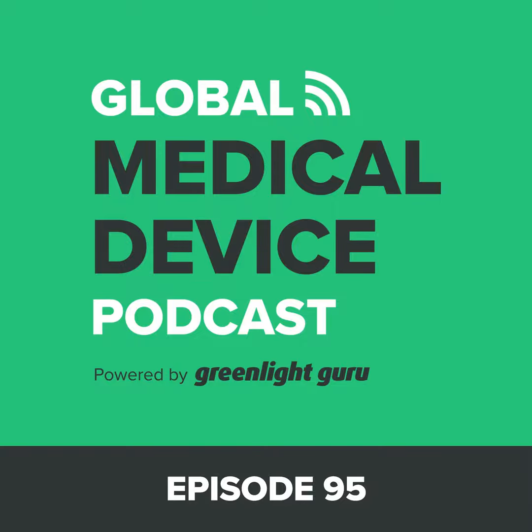I think one thing to pay attention to that also may be a point of confusion is the definition of use error versus user error. Use error is clearly defined in the FDA guidance, and there's a fundamental shift that has happened with that nomenclature.